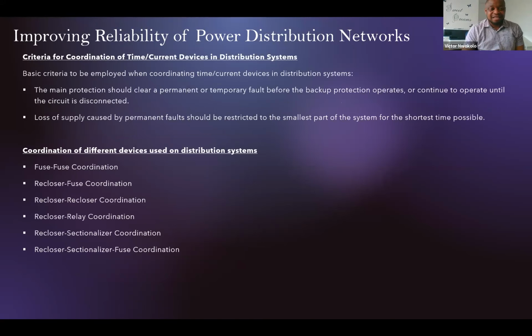Then my final point here, we also have to look at proper coordination, and there are a few criteria for coordination. And coordination, like I mentioned before, is where we look at how the entire protection criteria are carried out. The basic criteria to be employed is the main protection should clear a permanent or temporary fault before the backup protection operates or continues until the circuit is disconnected. Loss of supply caused by permanent fault should be restricted to the smallest parts of the system for the shortest time possible. So we have various types of coordination. We have fuse to fuse, fuse to recloser, recloser to recloser, recloser to relay, recloser to sectionalizer, recloser, sectionalizer, and fuse. Because of time, I can't go into each of these.